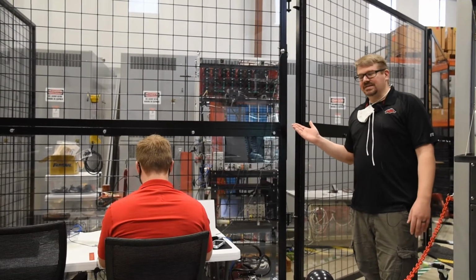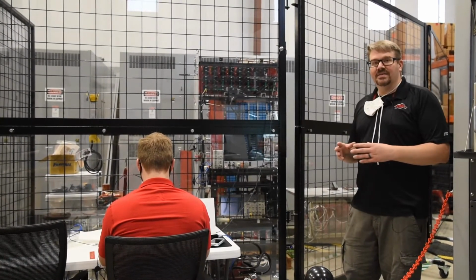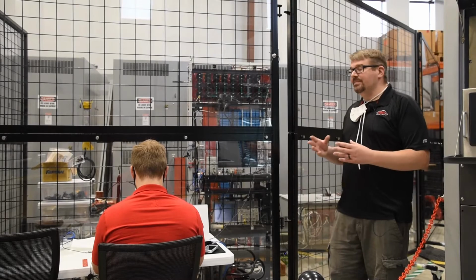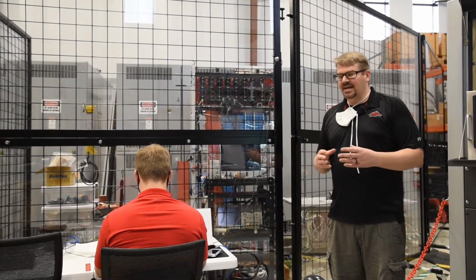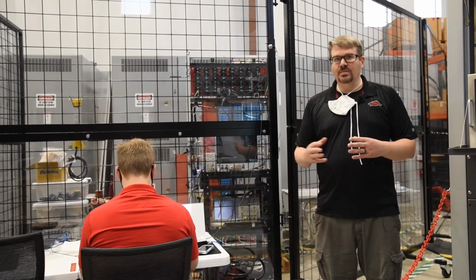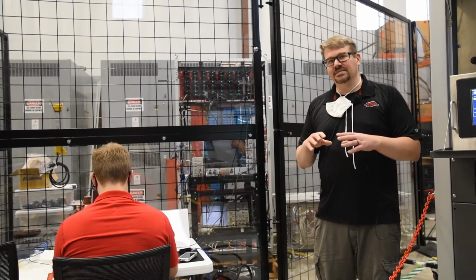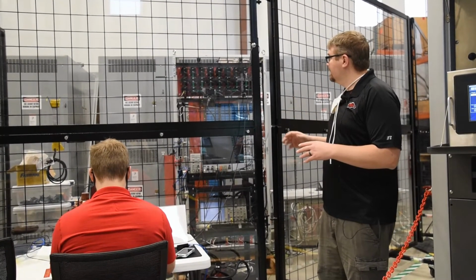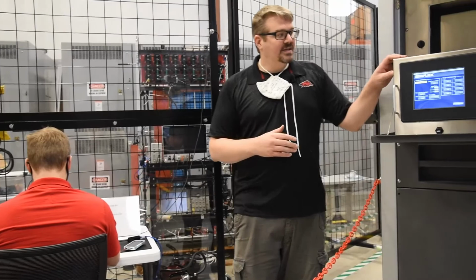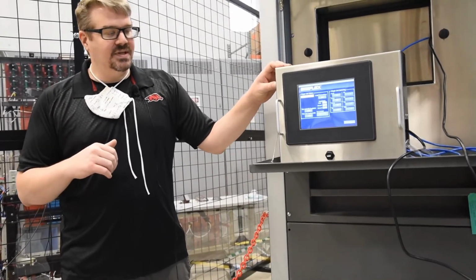So this is the MVUCSC project that we're testing here. This was fabricated at NCREPT, and we're doing some 13.8 kV testing on it this week. So the main purpose of this project is to kind of rebalance grid currents. So a lot of times people will have feeders in the distribution system, and they'll break off and feed a lot of single phase loads like homes or things of that nature, and those currents get unbalanced, which minimizes how much power can actually be transferred. So by rebalancing at the transformer using devices like this, we can actually maximize power transfer for the system. This system here is a 700 kilowatt AC load bank that we use in testing the MVUCSC project.